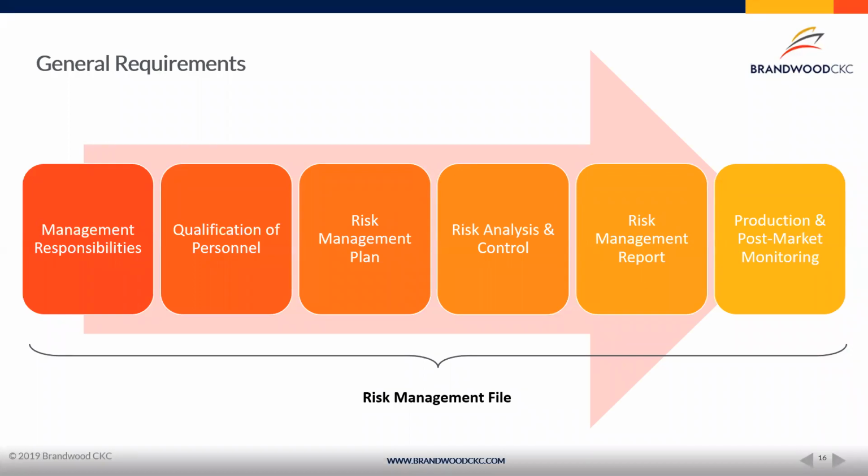We define who the people are who are responsible for making the decisions around whether a risk, harm, or hazard is there within your medical device. You have to show that those people are qualified, and that qualification of personnel is very important, because you can't just bring somebody in who says, yeah, I think this is low risk. You have to have some rationale for that.